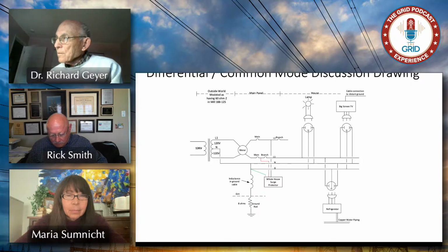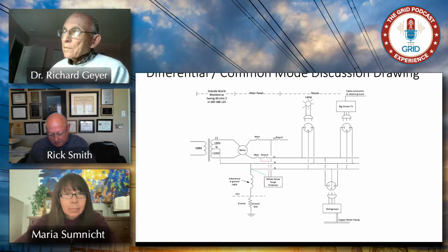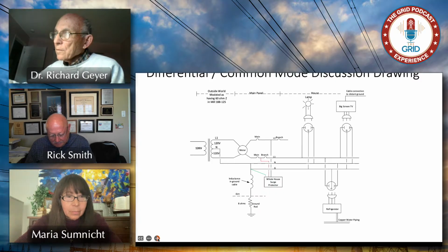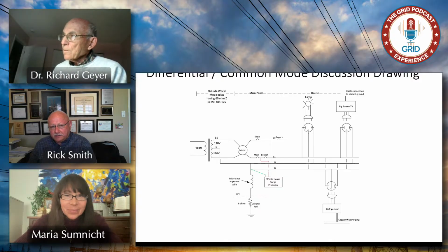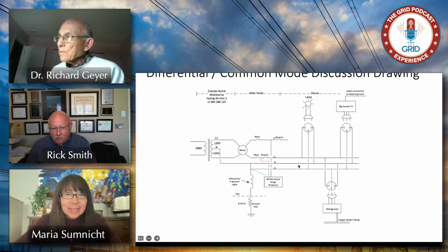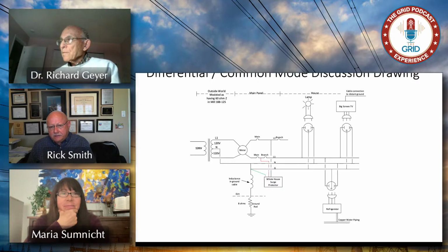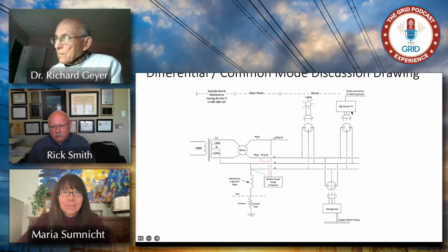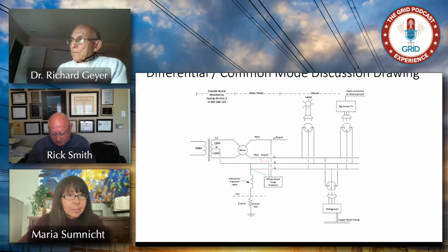I'm not disparaging whole house surge protectors. I wish I had one, because one thing they do a great job of is clamping the L1, neutral, and ground at the same potential, so you don't get a lot of voltage between the wires. So if you look at the light bulb, it has no external reference to ground. So as long as the voltage, even though it may be high, is the same on both wires going to the light bulb, there's no voltage across the light bulb and it's not under any stress.